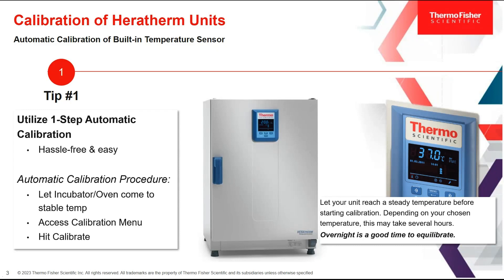It's good practice to make sure you've equilibrated your incubator or oven to the temperature you desire to calibrate at before starting this process. Equilibration time is really dependent on your lab, your temperature, where you started, and where you're going — it could take anywhere from under an hour to several hours to get a good, stable calibration temperature. A really great practice is to set your incubator or oven up overnight, because then it's not wasting your time. Let it equilibrate overnight so in the morning when you come in, you know your unit is ready to calibrate.